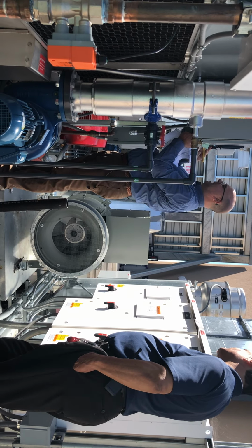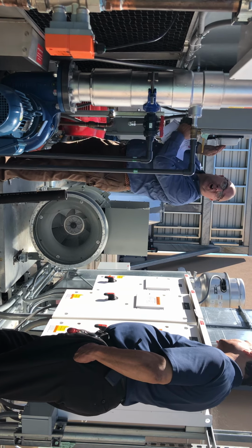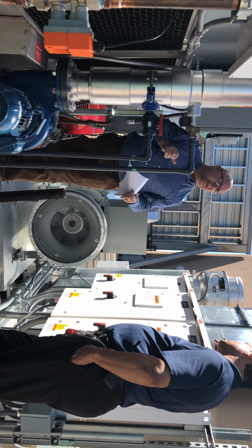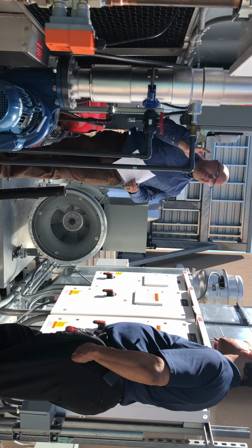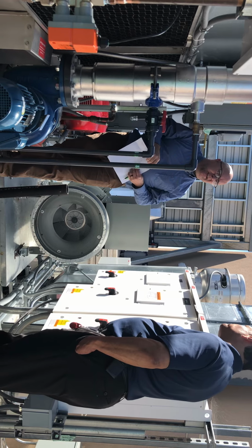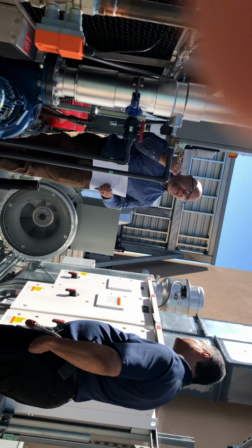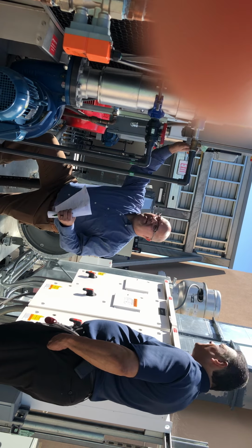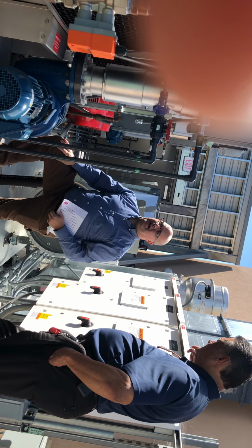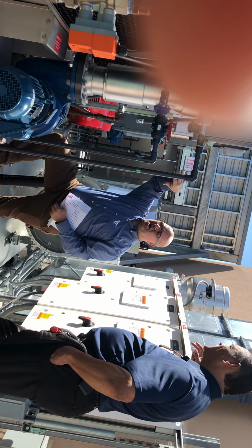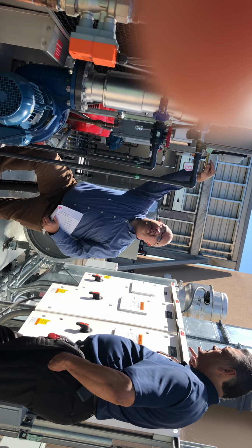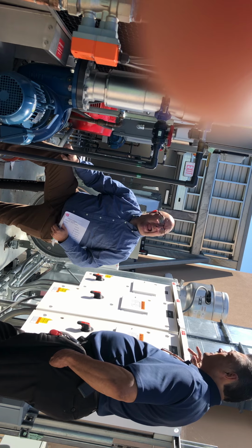Oh, you know what? The thing is, I don't have these turned on right now, so they're not lit up. This is also a little thing we're working out with the mechanical contractor. I'm supposed to have temperature control of these, but this is all kind of a built-in system. So right now, if it gets too hot, I turn on the cooling towers, and these controls here turn on the pump that pushes water over the media and speeds up and slows down the fans that are in there as well.